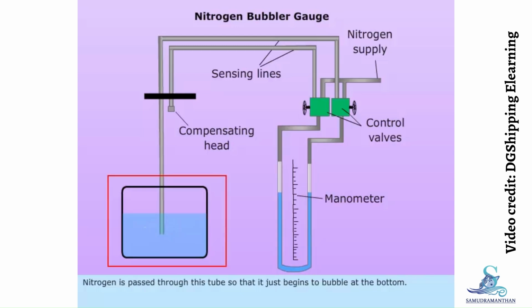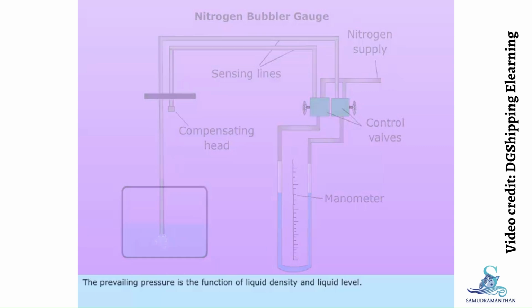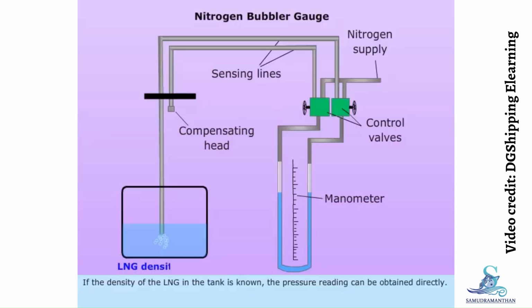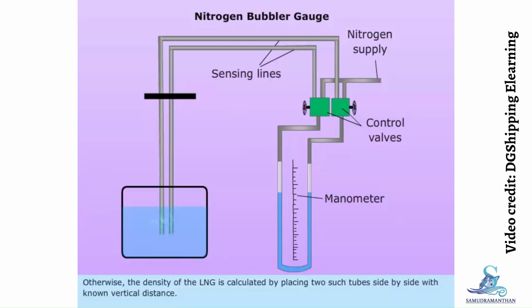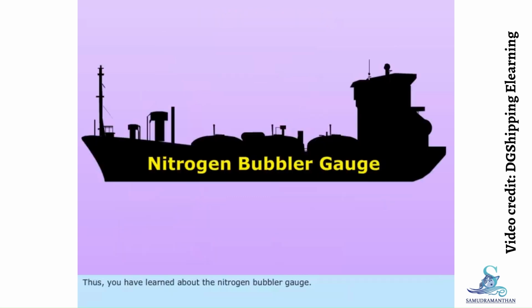Nitrogen is passed through this tube so that it just begins to bubble at the bottom. The prevailing pressure is a function of liquid density and liquid level. If the density of the LNG in the tank is known, the pressure reading can be obtained directly. Otherwise, the density of the LNG is calculated by placing two such tubes side by side with a known vertical distance. Thus, you have learned about the nitrogen bubbler gauge.